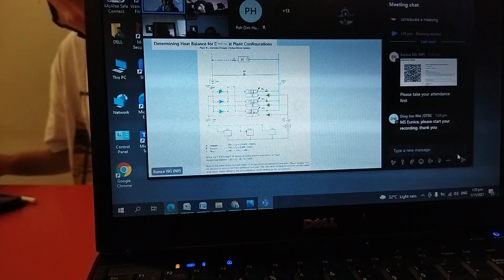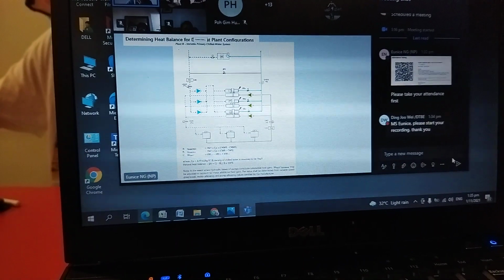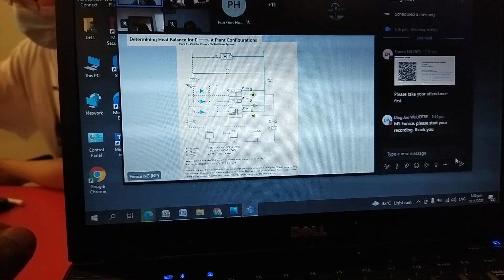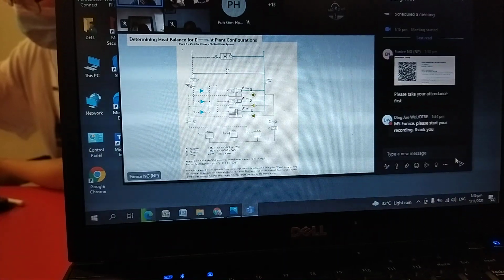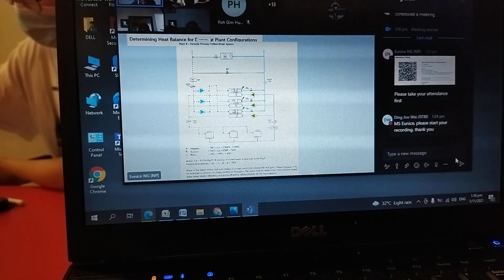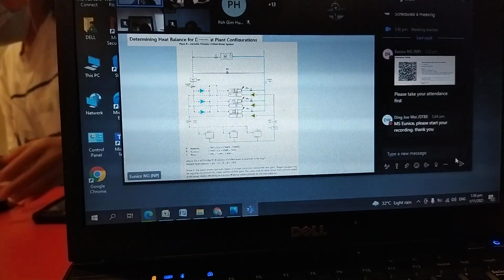side. This chill water pump is on the primary side. That means they supply water through a common flow, through a common header. When they supply water to a common pipe, they call this pipe the common header. Then all the water combined will go through here. So there's some advantage of taking the chill water flow. But this pump will have to pump water through the pump as well as the secondary loop.